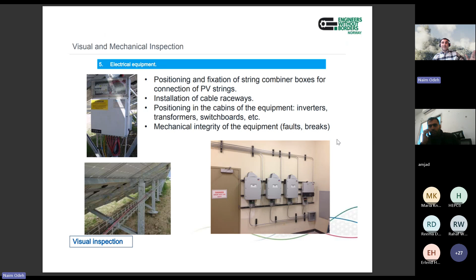And about IP rating, you see here in the picture a box, an enclosure for breakers with IP66. That's fine, good. But by having a bottom look at the cable entry, you see the opening around the cable. You see the white cables there, there are openings there. Such openings actually affect the IP of the enclosure itself. So as a testing engineer, this kind of work is rejected.